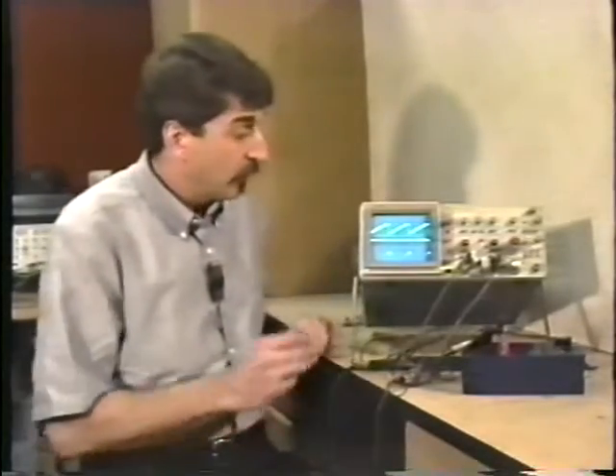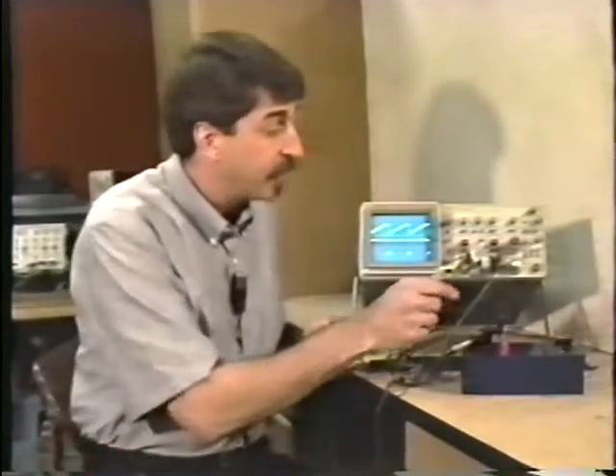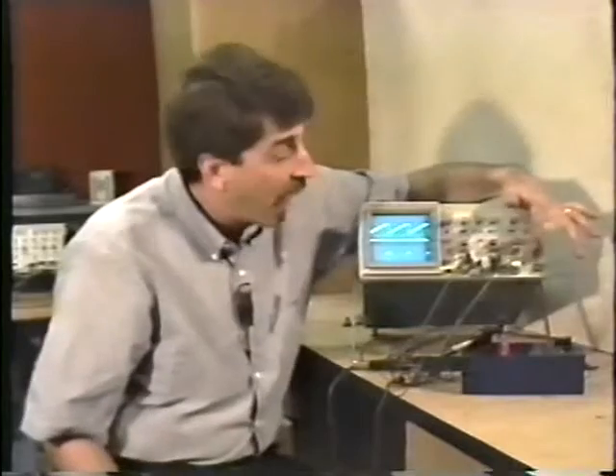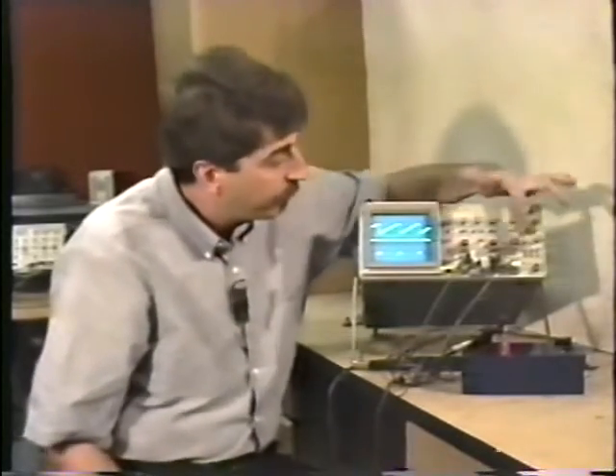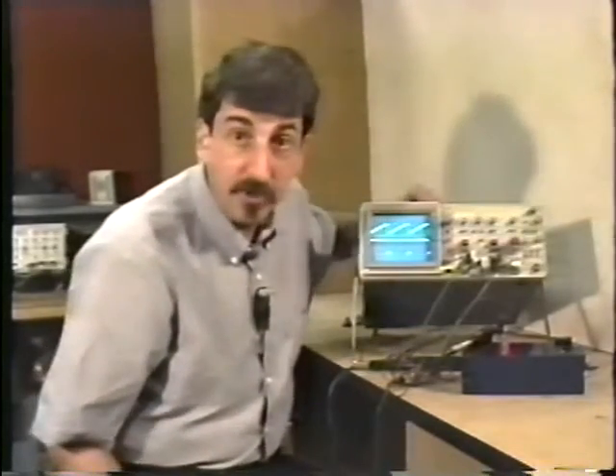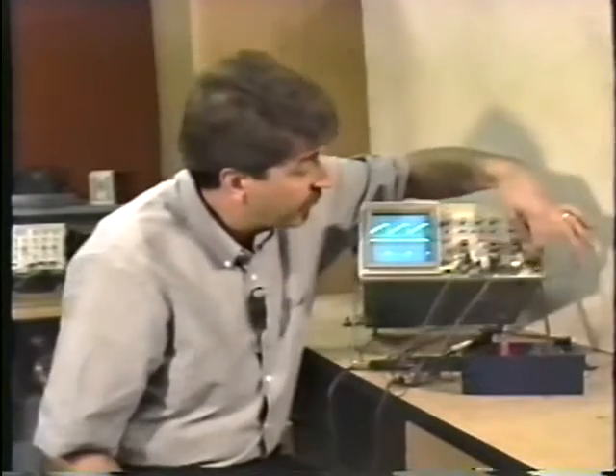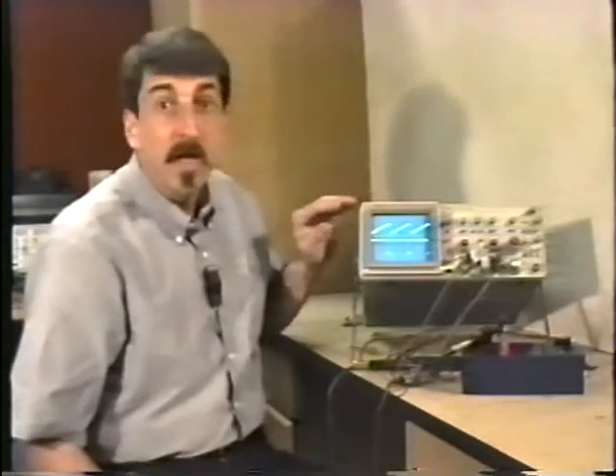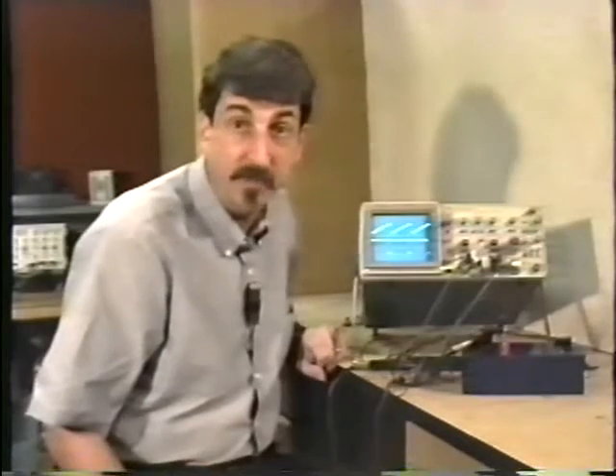Let's take a look at the internal first. And the internal refers to the two vertical inputs, channels 1 and 2. When the selector is set for internal, we can tell the oscilloscope where to look for the trigger signal by selecting either channel 1 or channel 2. In this oscilloscope, there's also another setting called vertical mode. And in the vertical mode, the oscilloscope selects both channels 1 and channel 2 as its trigger source.